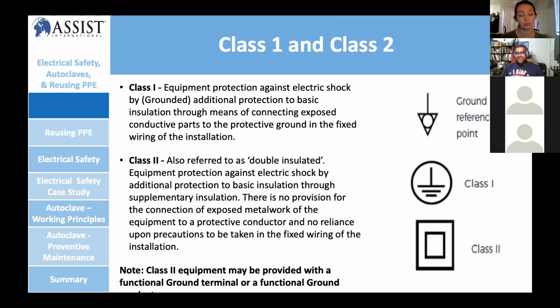Okay. And it's very rare actually. Sorry, class 2 is very rare? No, grounding for class 2. Actually for class 2 there's no grounding, but some designs intend to put the equipotential line together for the power supply purpose only, but it doesn't affect the ECG line. So there's isolation between the power supply and the device. For example, with an adapter using a separate power supply, the power supply is class 1, but the device is class 2, using a 12-volt connector. So they design it in such a way.